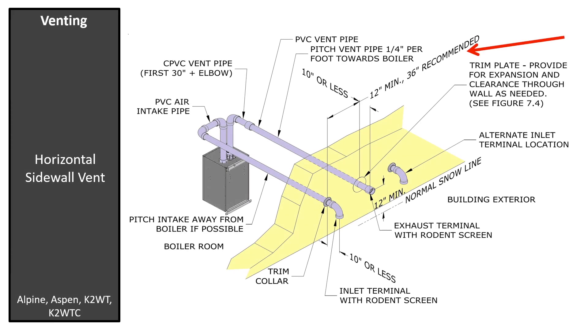Through the following slides, we will address the highlights of some of the venting techniques. Two-pipe sidewall: even though we have a minimum of 12 inches between the vent and air intake pipes, more separation is preferred to avoid possible cross-contamination of flue gases. On all venting, it is important to pitch the vent pipe towards the boiler to allow venting condensate to drain back to the boiler. All external piping terminations must be a minimum of 12 inches above anticipated snow levels. You may not vent under a deck or run the vent under the deck to the outside edge of the deck.